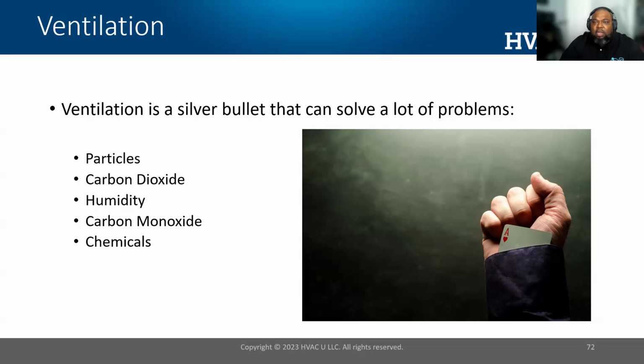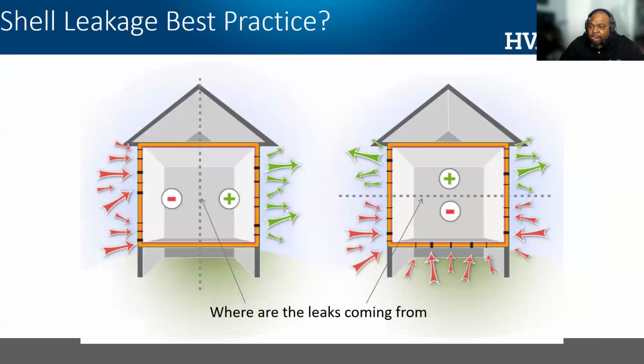All right. And ventilation done correctly is amazing. If you've ever been in a house that had an ERV or was well ventilated, your well-being was a lot better. Right? Now, old practices were where we would try to use the building shell for some type of leakage, and that isn't necessarily the best course of action. The trend now, or best practice, is to have a house as tight as possible, energy efficiency wise, and then have a robust and distinct ventilation plan to help control the ventilation.